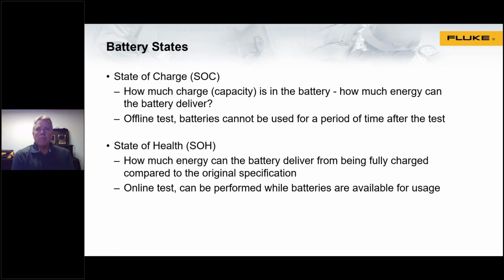Going to shift a bit, talk about battery states or battery health. And there's really two terms there that we're going to look at. One is called state of charge, or SOC is the acronym. It's really how much charge or capacity is in the battery. How much energy, when called upon, can the battery deliver? It's useful to know. However, it is an offline test. It's not a destructive test, but if you perform too many or too often state of charge types of tests, you need to have those batteries offline for one, so they can't be used when you're performing your test. But those tests can actually shorten the life of the battery. Also, after you've performed your state of charge test, the batteries cannot be put back in service for a period of time.